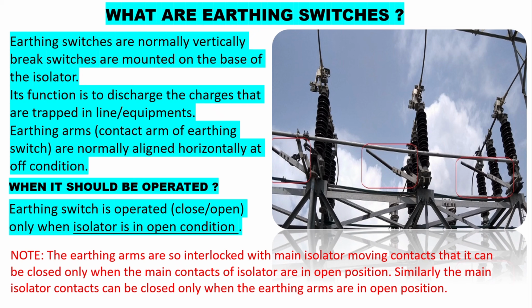Now comes what earthing switches are, what their functions are, and when they are operated. To understand earthing switches, it can be shown by a pictorial representation on the right hand side. As you can see, earthing switches are normally vertical break switches and they are always mounted on the base of the isolator. It is an integral part of the isolator and its function is to discharge the charges that are trapped in the line or the equipment. Earthing arms are normally aligned horizontally in off condition as shown here.